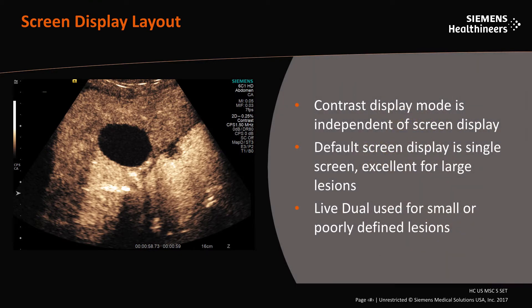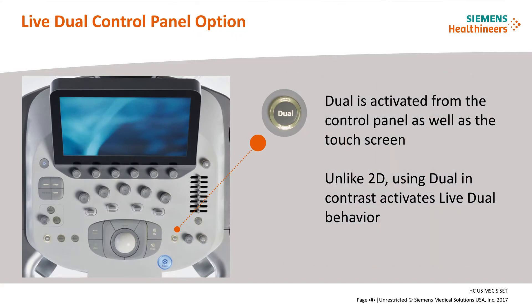Screen display layout is independent of the contrast display mode and is either single or dual screen. The default screen layout is single screen, which is excellent for large lesions. Live dual is an available option and is often used with smaller or poorly visualized lesions. There are two options for activating dual screen. Option one: from the touch screen, select live dual to split the screen and simultaneously display the contrast image on the left side and the 2D image on the right side. Option two: select the dual key on the right side of the control panel to activate the live dual display. The on-screen layout of the contrast image versus the 2D image is in a fixed position with no reversal.